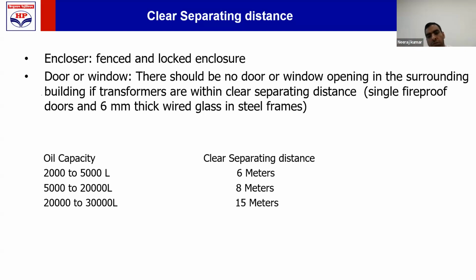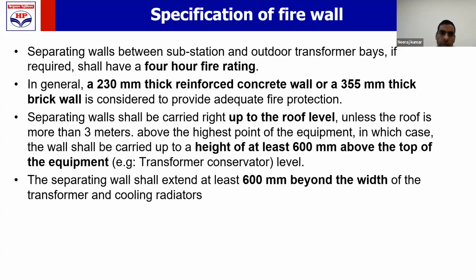Otherwise, go for clear separating distance. Nothing should come in that range. Now you are not providing clear separating distance. You thought, let us provide a separating wall. So how should that separating wall be? That separating wall should have a 4-hour fire rating. 4 घंटे की रेटिंग. 4 घंटे फायर चलता रहे. Your wall should be able to sustain.